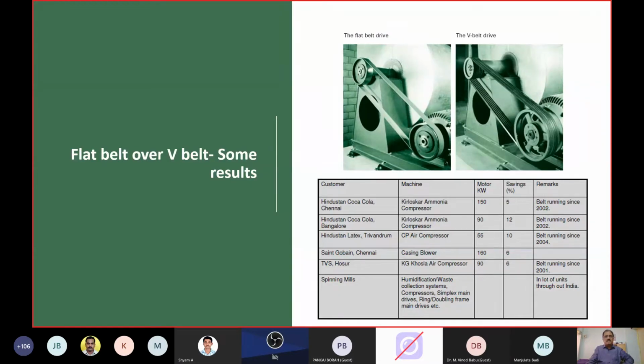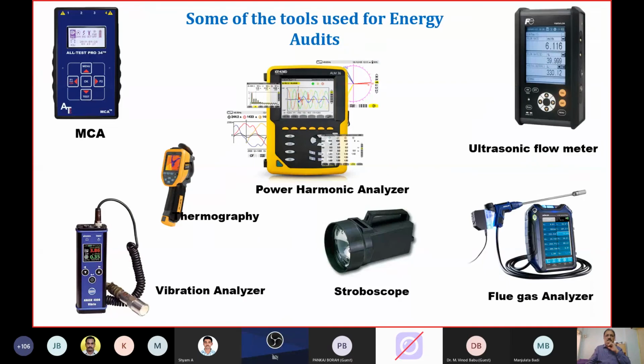So, one slide on how the power transmission element can offer you energy saving. As you can see here, for a continuously loaded fan application or a belt-driven pump application, replacing the existing V-belt with a flat belt or compact V-belts nowadays, you will be able to achieve up to 5% energy saving minimum. So when one undertakes a replacement of a motor, one can also consider including the transmission element so that the total energy saving potential is augmented. 3 to 5% becomes 5 to 9%. This is the choice available.